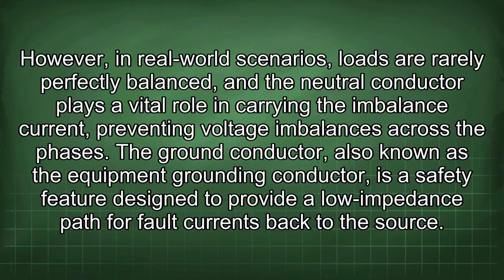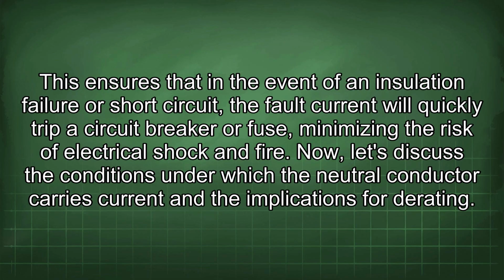The ground conductor, also known as the equipment grounding conductor, is a safety feature designed to provide a low-impedance path for fault currents back to the source. This ensures that in the event of an insulation failure or short circuit, the fault current will quickly trip a circuit breaker or fuse, minimizing the risk of electrical shock and fire. Now, let's discuss the conditions under which the neutral conductor carries current and the implications for derating.